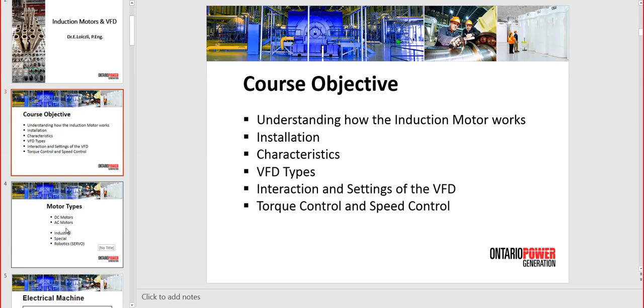In this case, the VFD will move around from one motor to another, so it will be used for different motors. And that's where you need to pay attention if the VFD is properly set up, especially if you have a VFD that is not a simple volt per hertz type. If it's a scalar type, volt per hertz, the settings are pretty easy to achieve. But if it's actually a vector control or direct control, then you need to have certain steps in mind, like parameter identification of the motor. So we will go through this, and I will explain what the difference is and how we can set up the VFD properly if we use a VFD.